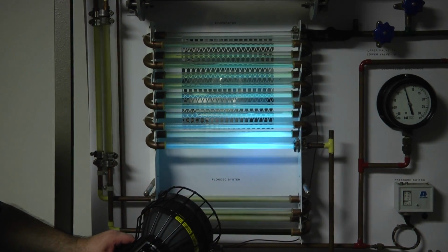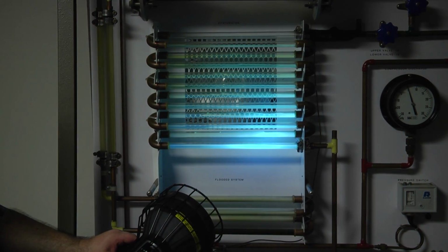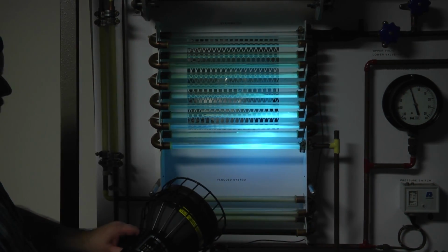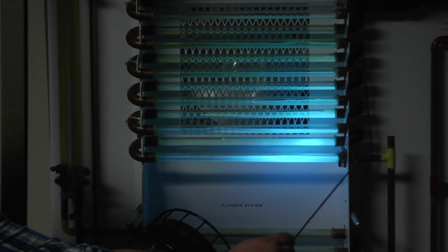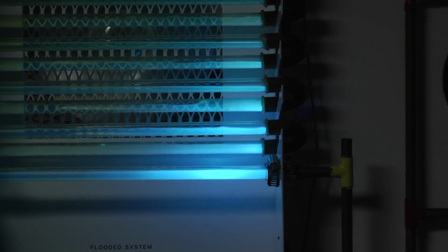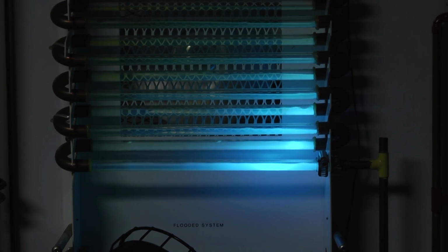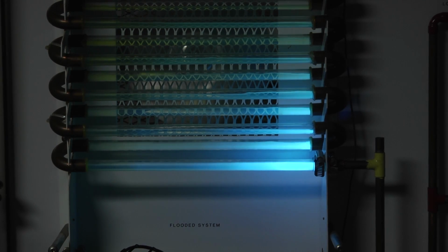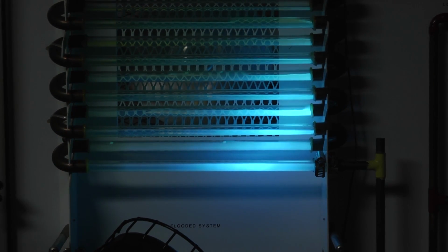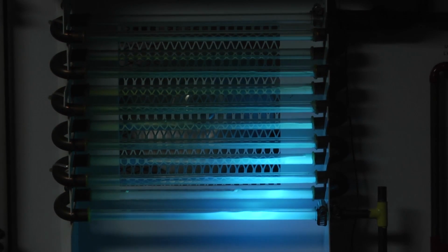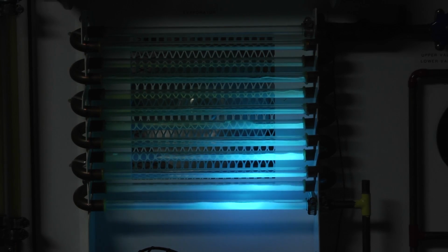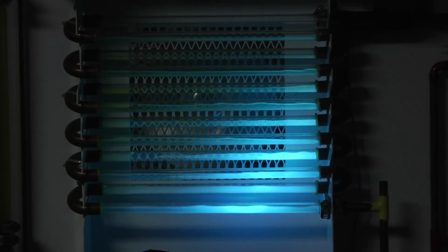The first portion of the system we'll talk about is the evaporator and what takes place in the evaporation process. Liquid refrigerant is fed to a metering device. The metering device, which sits outside of the evaporator coil, dramatically drops the pressure and the saturation temperature of the refrigerant, which leads to some of it immediately boiling off due to the rapid temperature change. This rapid boiling of refrigerant is called flash gas. And in an average refrigeration system used in air conditioning, about 20% of the refrigerant boils immediately to flash gas.